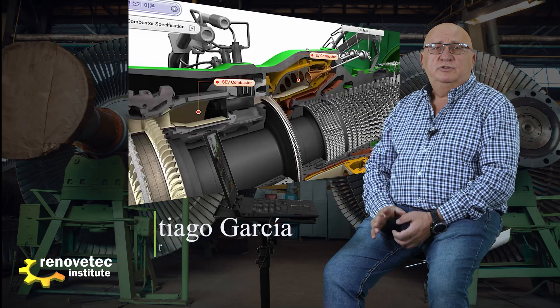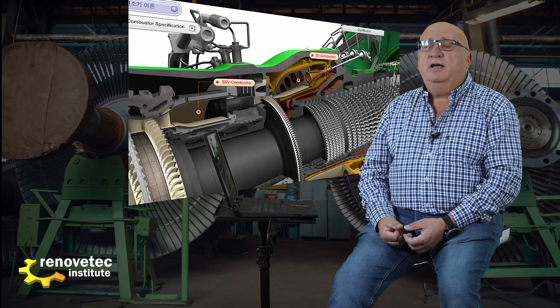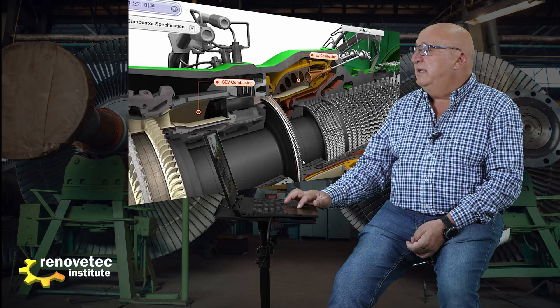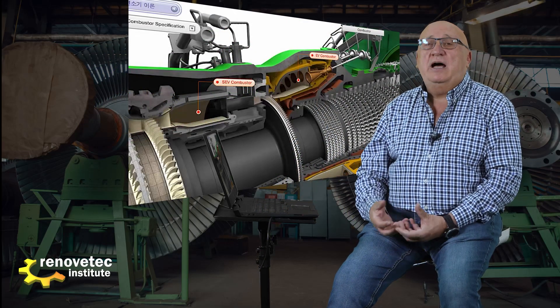The combustion chamber of this turbine is very unusual — it is not the most common configuration. First, it is an annular combustion chamber, meaning all combustors share the same space in an annular configuration. This differs from the can-annular configuration, where every combustor has its own separate space.